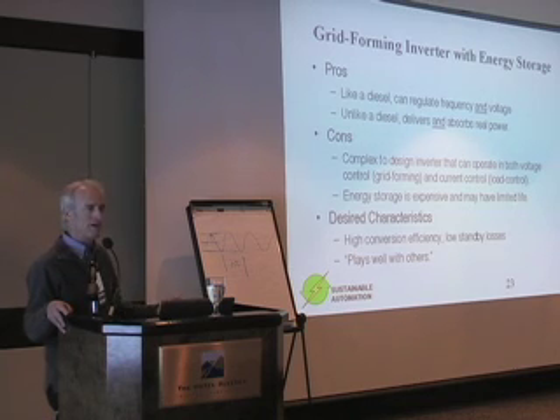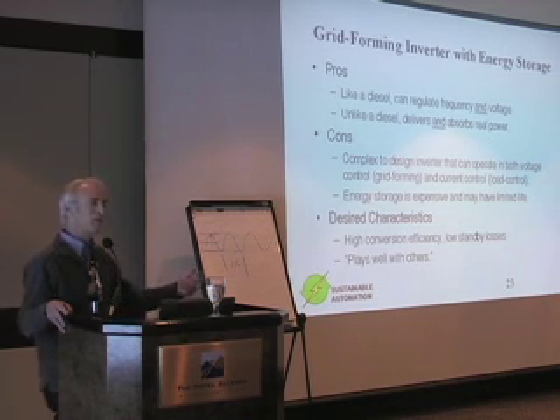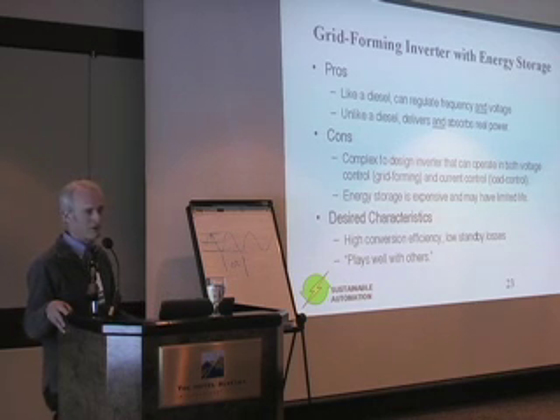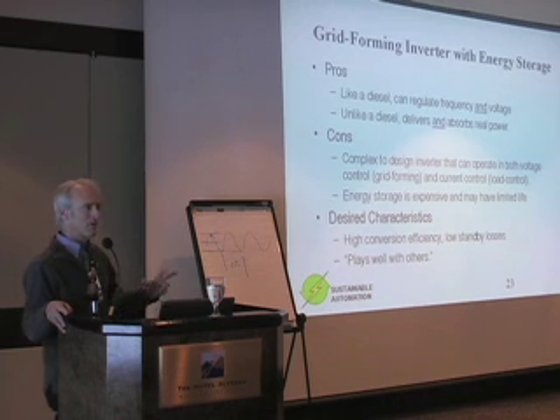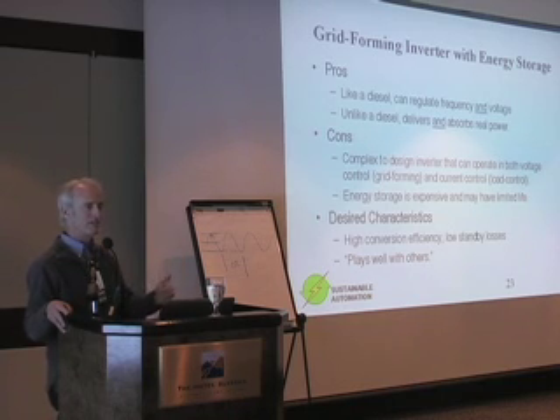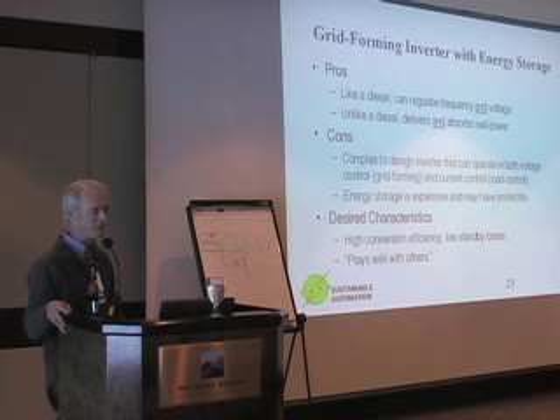But it does the diesel one better in that it can deliver or absorb both real and reactive power. And it can deliver real power while absorbing reactive power. That's called a four-quadrant power converter. So you've got real power, reactive power, either positive or negative in each. So you can see you have four possible combinations, whether you're delivering positive real power and positive reactive power, or positive of one form and negative of the other form.